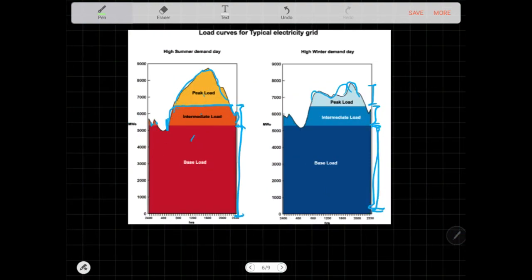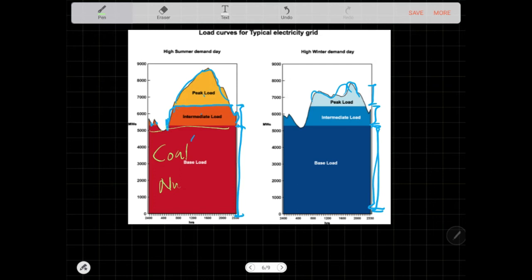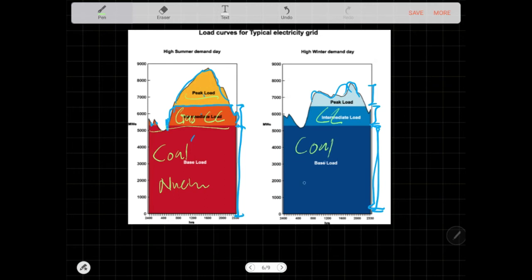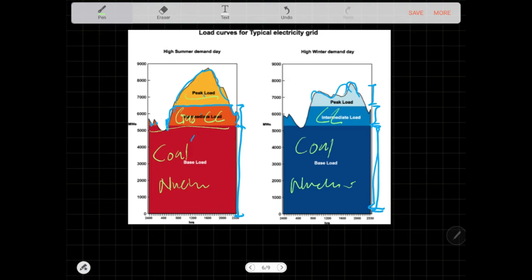Let's look back into the curve. Here is where all your coal and nuclear comes in. Your gas combined cycle and maybe your peaking plants come up here. Same case here, combined cycle, your coal and your nuclear. Why I did not mention any renewables? The first thing about renewables is that they do not follow your schedule. You cannot make them do something that they do not. They come as they want and they go as they want. For wind it's when they do have wind, and for solar it's when they do have sun.